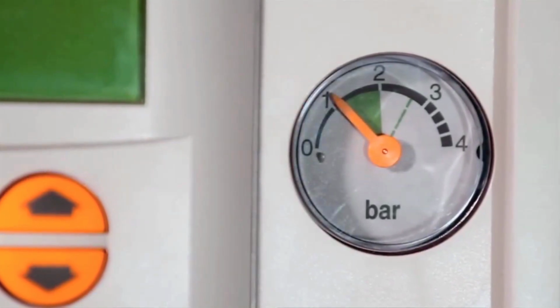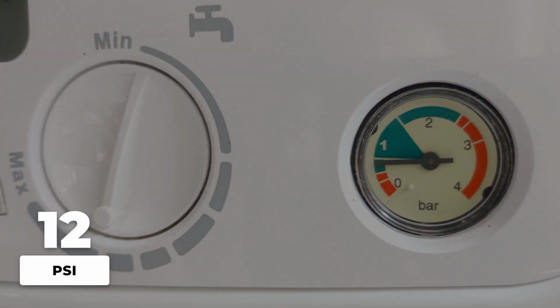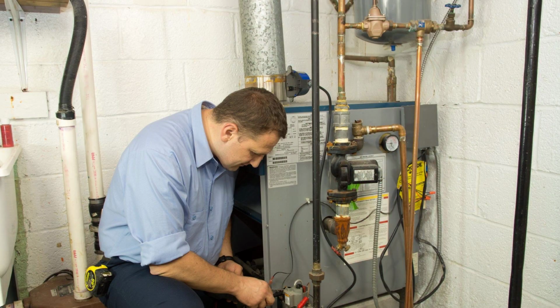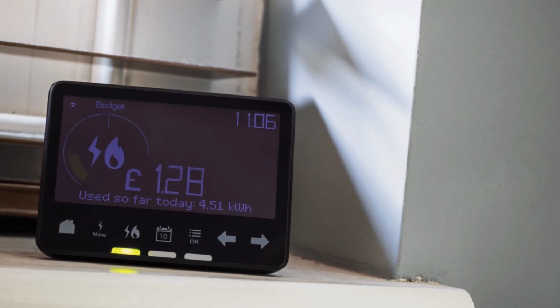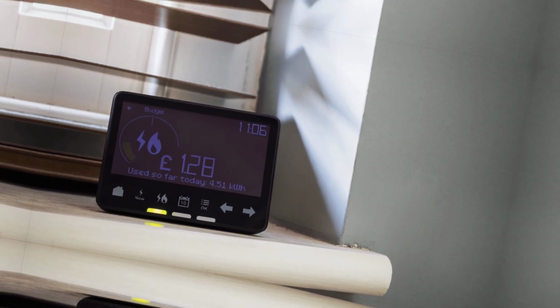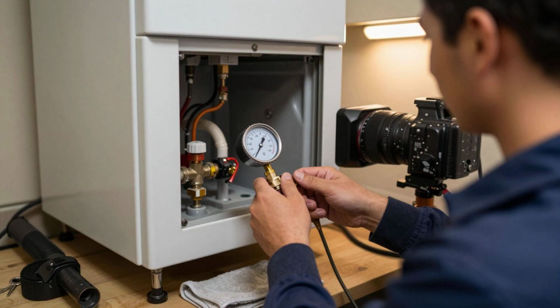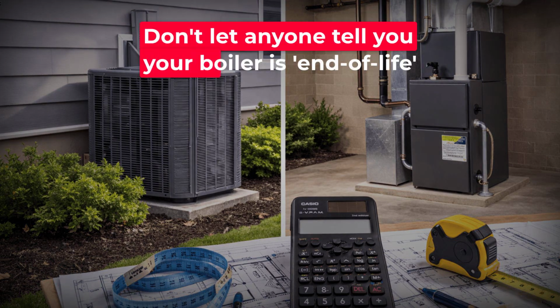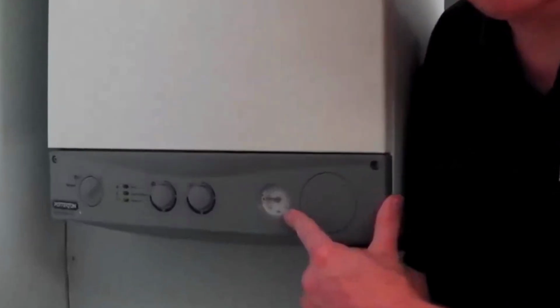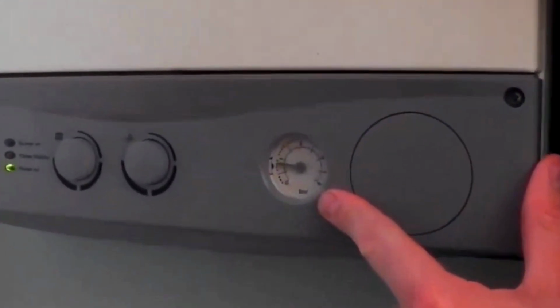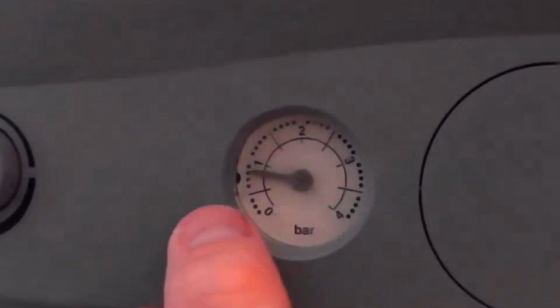Follow up with a glance at the pressure gauge. If it is below 12 pounds per square inch when cold, top it off through the filling loop. This routine, costing $0, can add up to 5 years to your boiler's life and slash fuel waste. If the pressure keeps dropping after bleeding, that is when you call a professional. Do not let anyone tell you this is end of life. It is basic upkeep the industry hopes you will overlook.